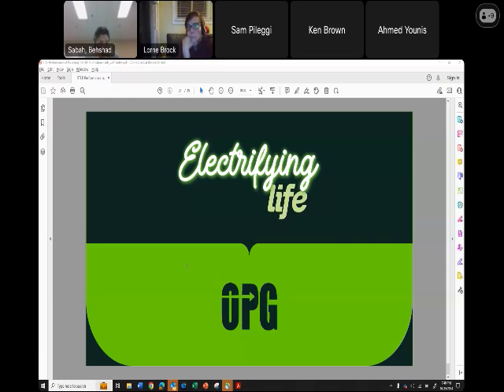Is the Hilliard system out of service? The intent was to no longer use the Hilliard dry IX resin along with the EPT ICB resins. But in practice, in many cases, we did valve them out and we're using them in parallel. In my opinion, the Hilliard dry IX are probably long depleted and basically don't do anything. They're just sitting there, taking up space, basically.